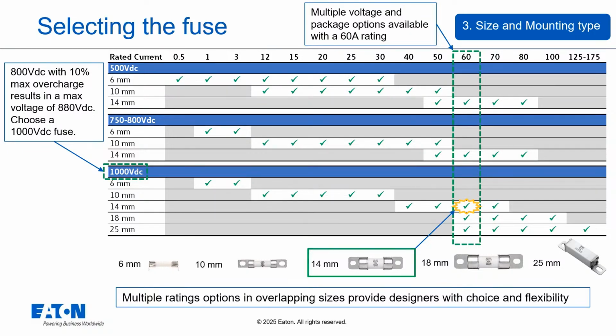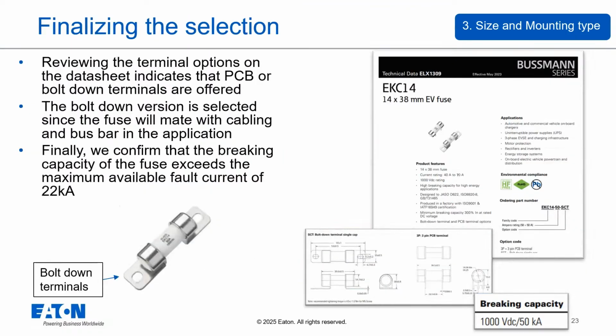Moving on to finalizing the selection, we look at the mounting type. Checking the datasheet for our chosen fuse, it offers options like PCB mount or bolt-down terminals. Since this fuse is connecting to cabling and bus bars, the bolt-down version is the right choice for the application. Finally, and very importantly, we confirm the fuse's breaking capacity. This is the maximum fault current the fuse can safely interrupt. In our example, the maximum available fault current was 22,000 amps. We must confirm that the selected 60 amp 1000 volt bolt down fuse has a breaking capacity that exceeds this 22,000 amp fault current, which it does given the 50 kA rating from the datasheet.